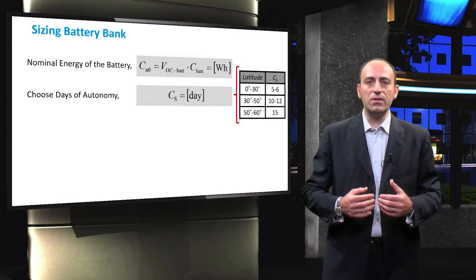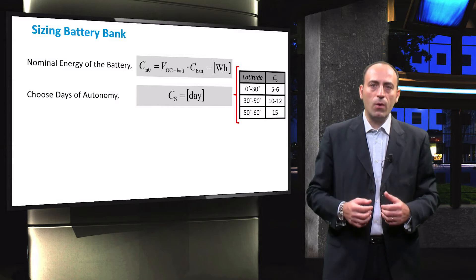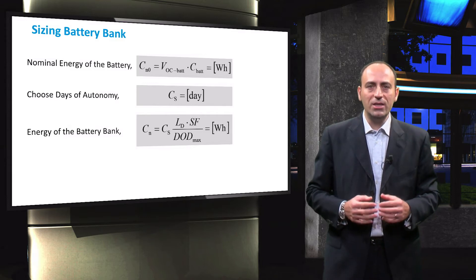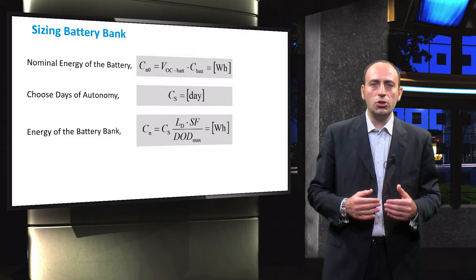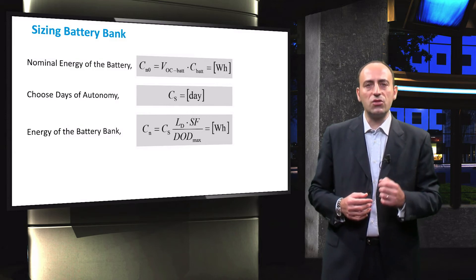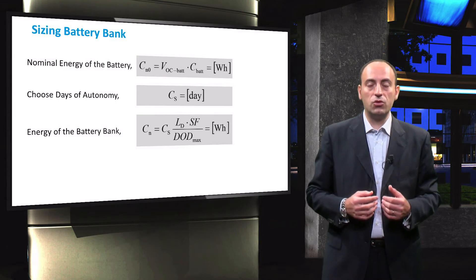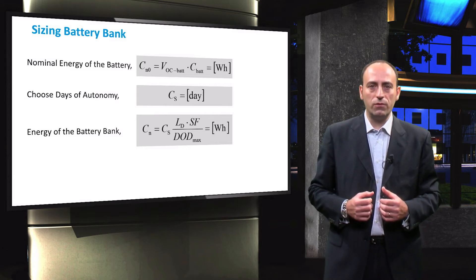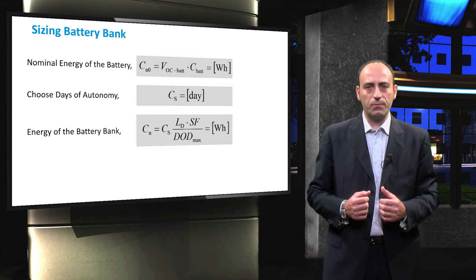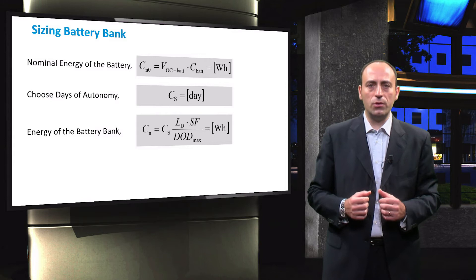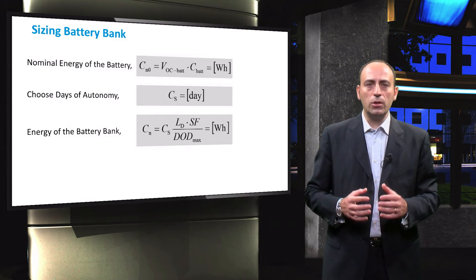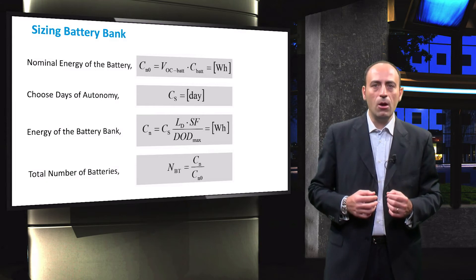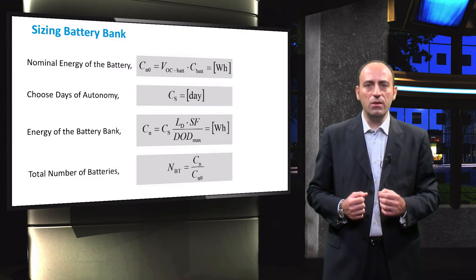The number of autonomous days increases for higher latitudes. Next, the required total energy of the battery bank, CN, is determined. It is calculated by dividing the product of the daily energy demand of the loads, the chosen autonomous days, and a sizing factor, SF, by the maximum depth of discharge, DOD max. Here, DOD max is the maximally allowed depth of discharge of the batteries in order to prolong battery life, and it is normally chosen between 20 to 30%. Finally, from CN, the total number of required batteries is calculated by dividing the total energy of the battery bank, CN, by the rated energy capacity, CN0, of a single battery.